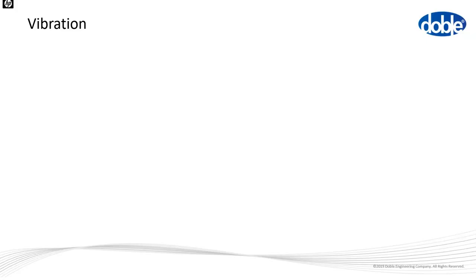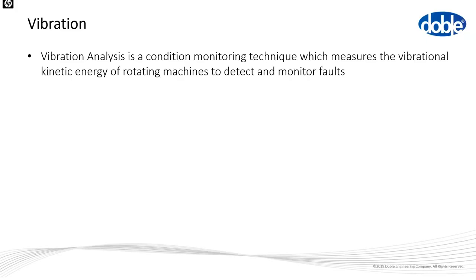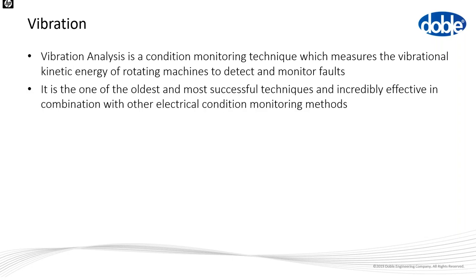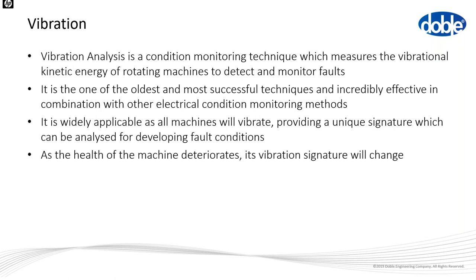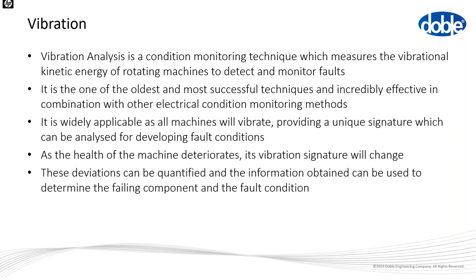Moving on to vibration monitoring — measuring the vibration kinetic energy of rotating machines. It's one of the simplest, oldest, and most successful techniques, especially when used in combination with other monitoring methods. It's widely applicable because all machines vibrate, and each machine vibrates with a unique signature that can be analysed for developing fault conditions. As the vibration signature changes, it gives a good indication of changes developing inside the machine. By quantifying those deviations you can determine which component is failing and what the fault condition is.